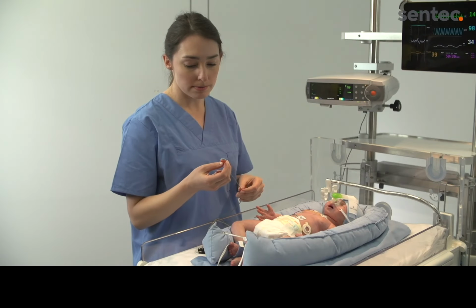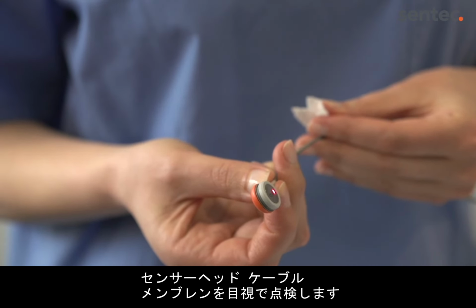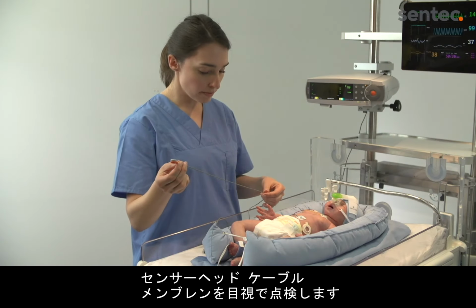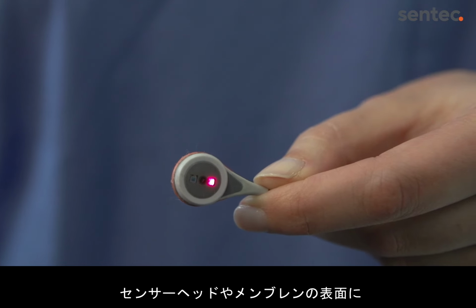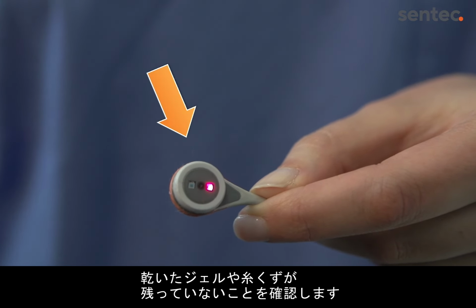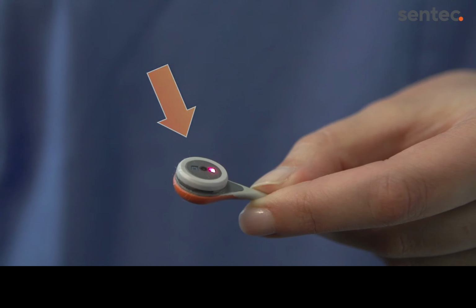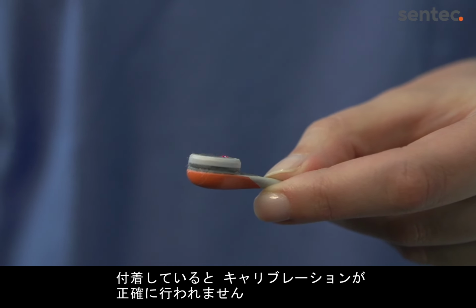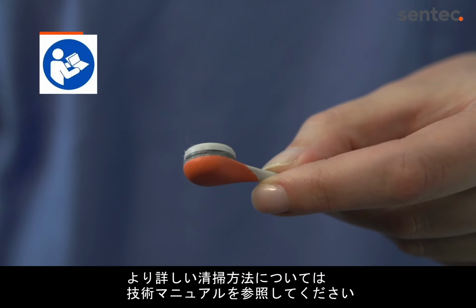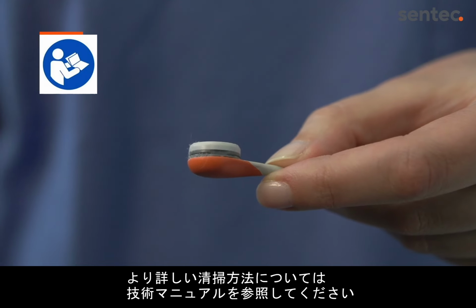After cleaning the sensor, visually inspect the sensor head, cable, and membrane. First, ensure that there is no remaining dried gel or lint residue on the sensor head or membrane surface, which may result in an unsuccessful calibration. If needed, refer to the technical instructions for more extensive cleaning steps.